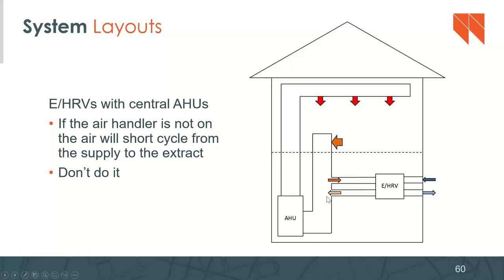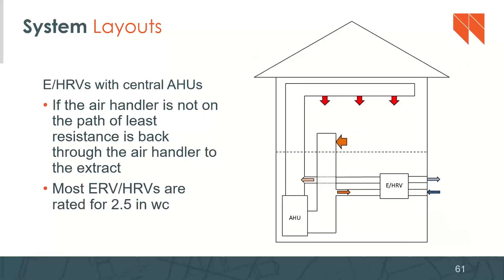We're telling you, don't do this. Don't do this because it's going to short cycle, right? If you're pushing the outside air into relatively the same space that you're pulling inside air out, you probably are going to pull a large portion of your fresh outdoor air right through and back out the building, which we don't want to do. We want that fresh air to make its way into the space, and into the occupants, right? So how can we do that a little better?